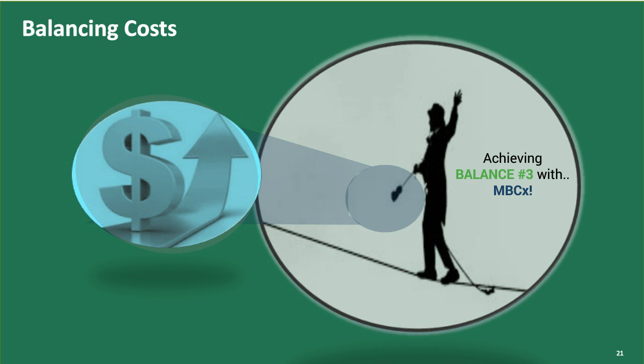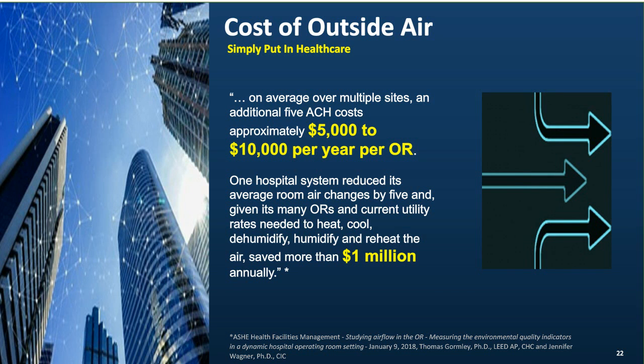You want to look at energy from the cost of the outside air. Simply put, in healthcare, on average, if I increase the air change rate by 5 changes per hour, I am increasing that OR, depending upon its size, from $5,000 to $10,000. This isn't my data, guys - this is actual real measurements that occurred in studies out there by ASHE just recently last year.